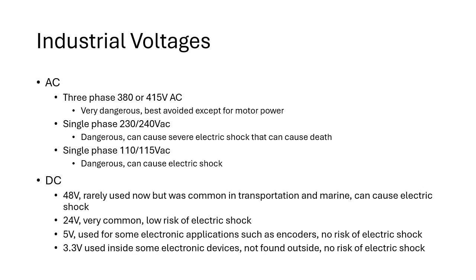So for example, we might see a three-phase input coming into, say, a VFD or a control panel. It might be 380 volts or 415 volts AC. That's a very high voltage. We can manage that voltage into smaller voltages using transformers. And the reason we use these high voltages is that the higher voltage gives us more power at a lower current. The alternative is, if we have much lower voltages, we'd need much thicker cables, which would be more difficult to install, more difficult to manage, and of course more copper, so it would be more expensive.